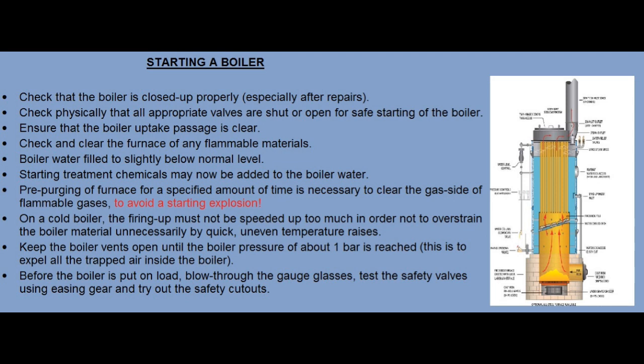Keep the boiler vents open until the boiler pressure of about 1 bar is reached. Before the boiler is put on load, blow through the gauge glasses, test the safety valves using easing gear, and try out the safety cutouts.